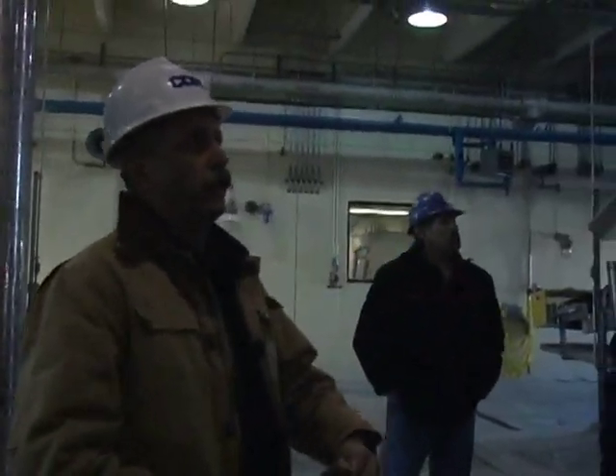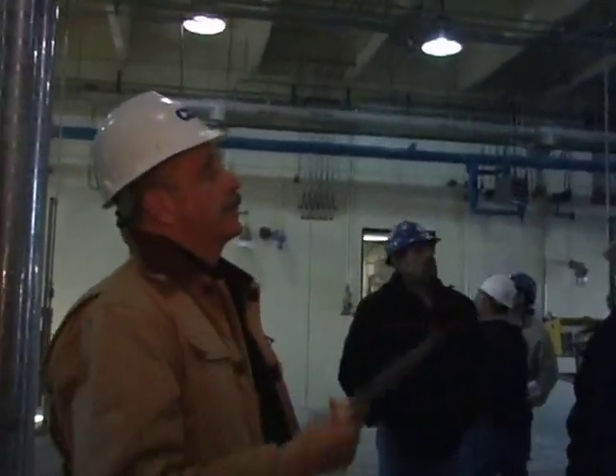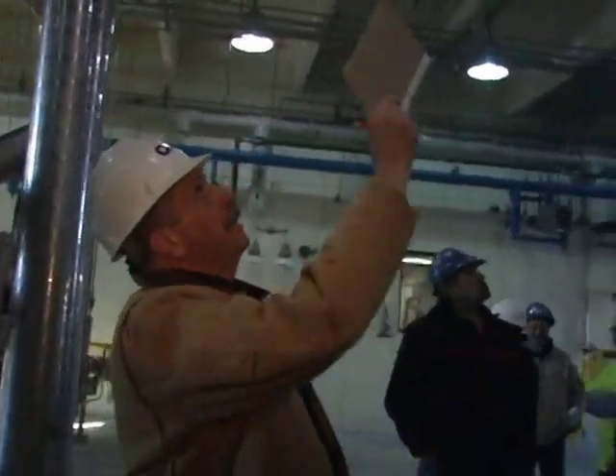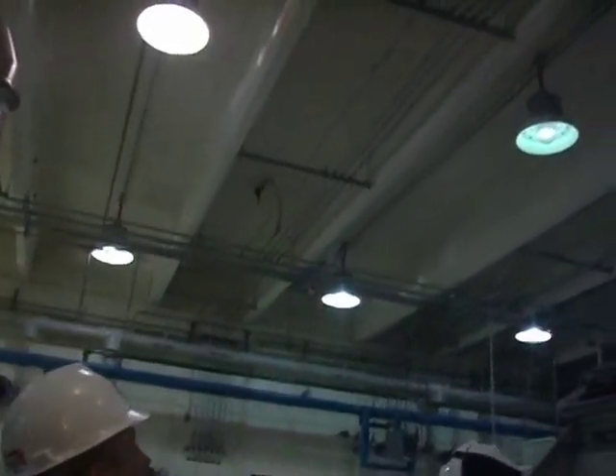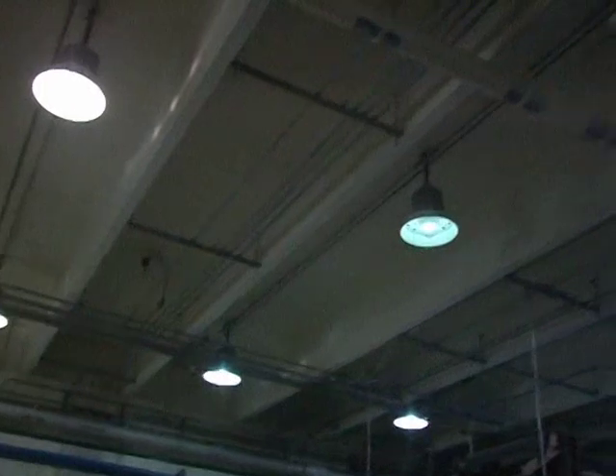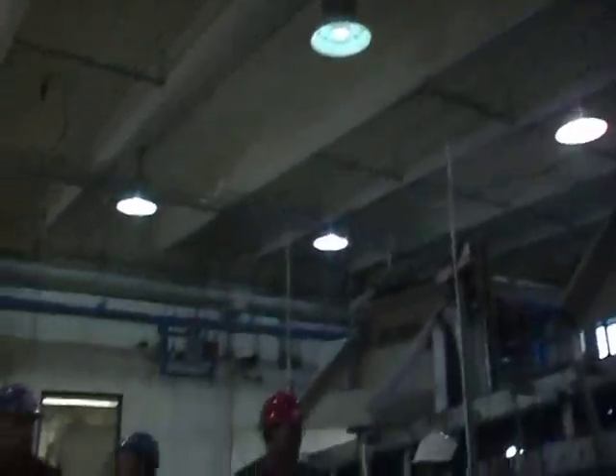Continue a little bit on the support systems within the building. Again, up at the ceiling, you've got heat detectors. There are, I believe, 6 of them within this room. So if you get into a situation here where you've got a fire situation, you will get an alarm at the fire alarm control panel, which is also fed back to SCADA, and I believe that's monitored off-site as well to the fire department.